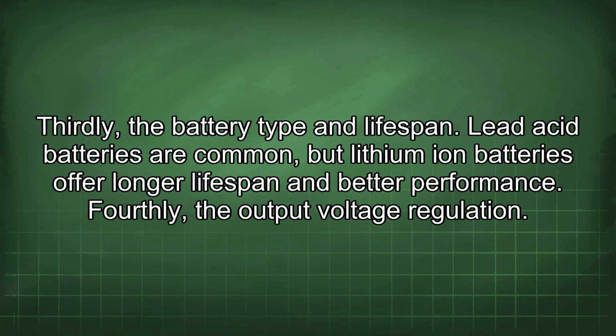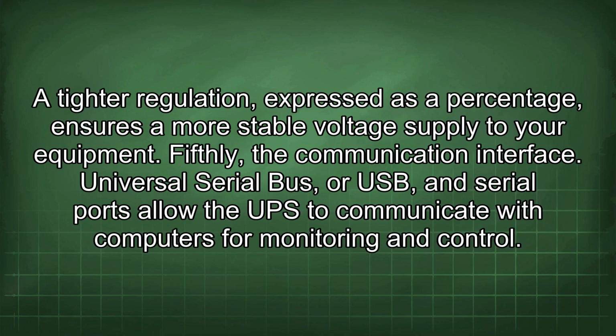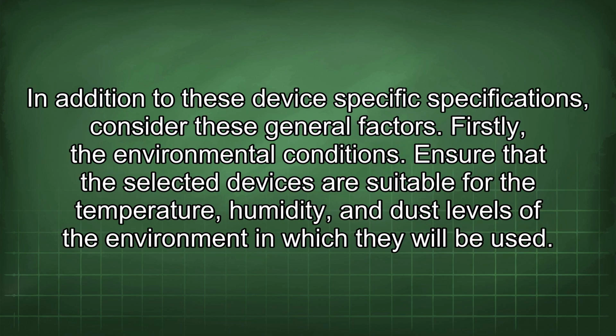Thirdly, the battery type and lifespan. Lead-acid batteries are common, but lithium-ion batteries offer a longer lifespan and better performance. Fourthly, the output voltage regulation. A tighter regulation, expressed as a percentage, ensures a more stable voltage supply to your equipment. Fifthly, the communication interface. Universal Serial Bus, or USB, and serial ports allow the UPS to communicate with computers for monitoring and control. In addition to these device-specific specifications, consider these general factors.